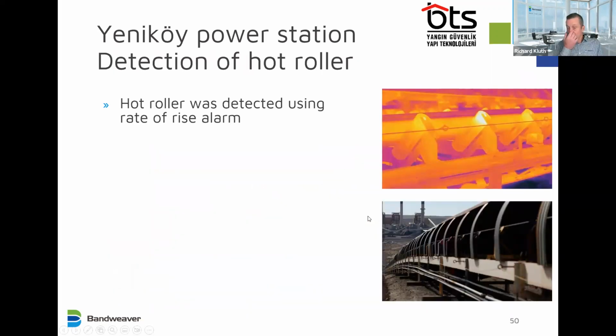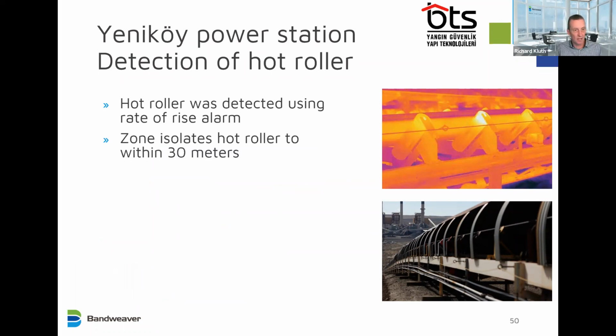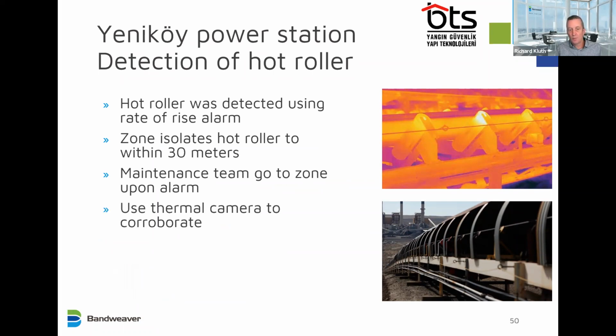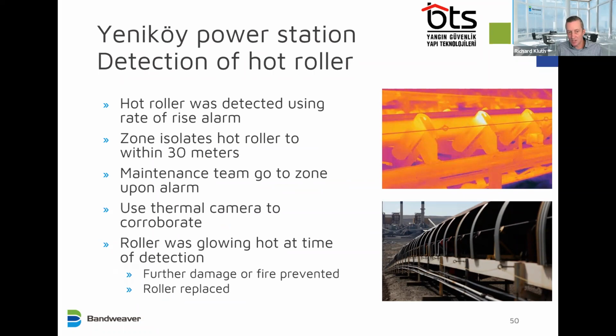In this case, within the first 12 months of installing the system, a hot roller was detected using the rate of rise alarm, and a fire was prevented. So it's already proven to be very useful. When the hot roller was detected, it was isolated to within 30 meters. The maintenance team go to the zone upon alarm, use a thermal camera to corroborate, and then take the action. In this case, the roller was glowing hot at the time. It was very easy to spot even without the camera. And the roller was replaced, and further damage and fire was prevented in this case.